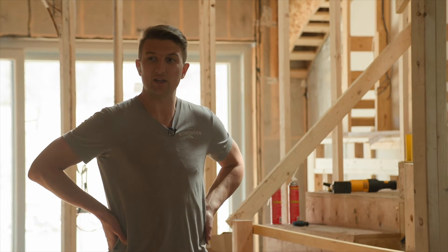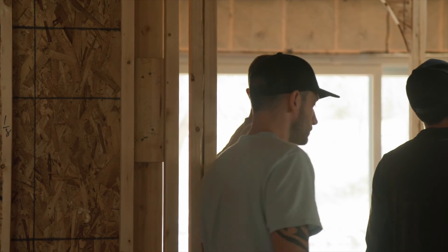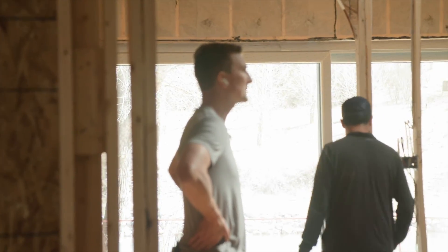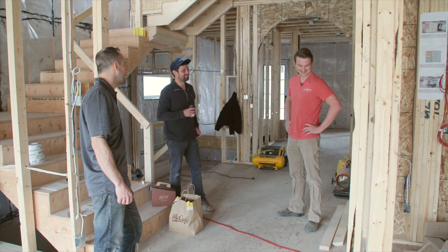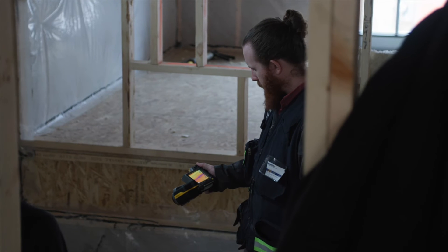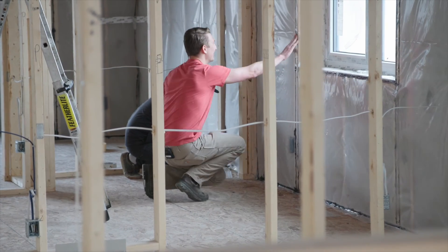We got it down to 1.1. In this house, we did two blower door tests - three guys including myself going around with tapes, caulking, feeling spots while the blower door was on, using the IR camera, investigating every single nook and cranny. Each guy was here for at least three or four hours. Those are hours that are very necessary for getting a product from regular code-built to a very high performance airtight home. You only get one shot at that - there's no going backwards.